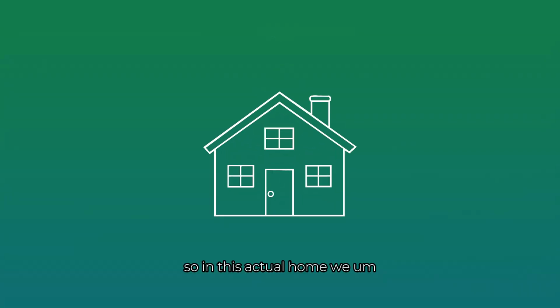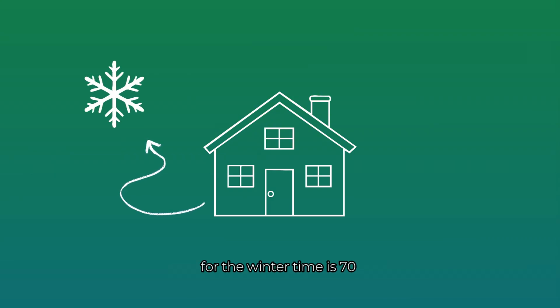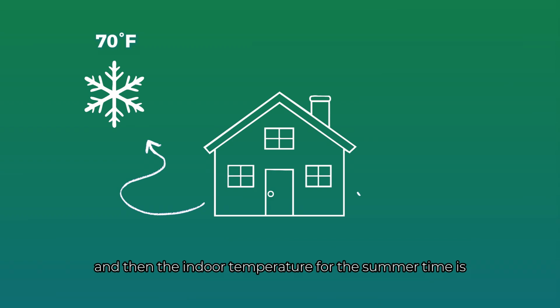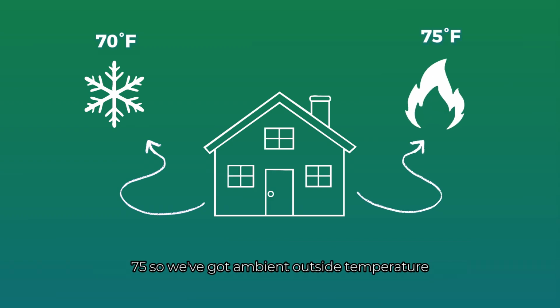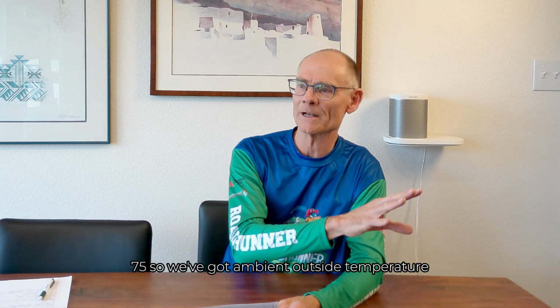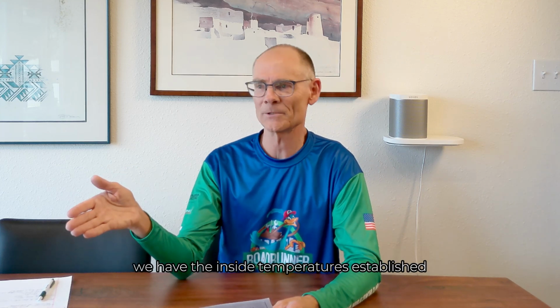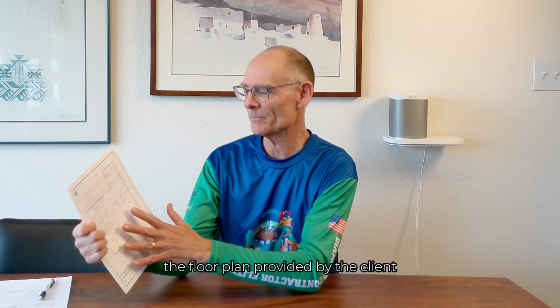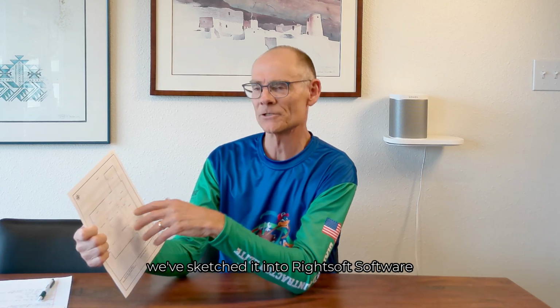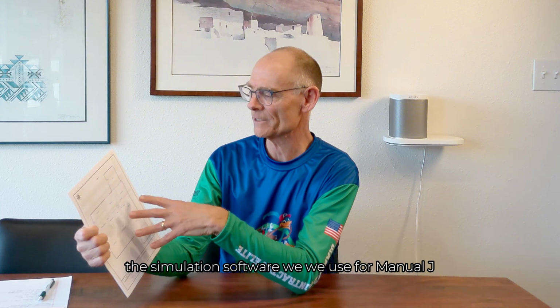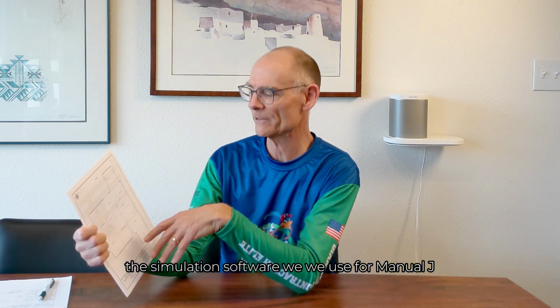So in this actual home, we selected the indoor temperature for the wintertime as 70 degrees, and the indoor temperature for the summertime as 75. So we've got the ambient outside temperature, we have the inside temperatures established, and now we can take the floor plan provided by the client. We've sketched it into RightSoft software, the simulation software we use for Manual J, and now we can do a load calculation.